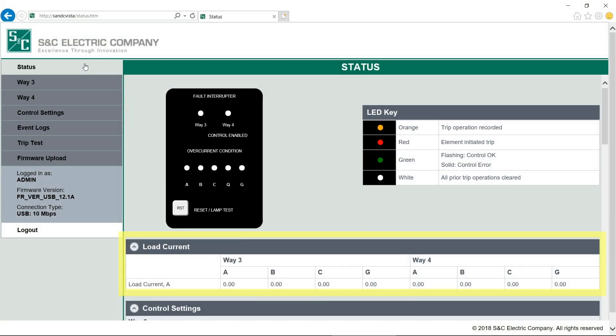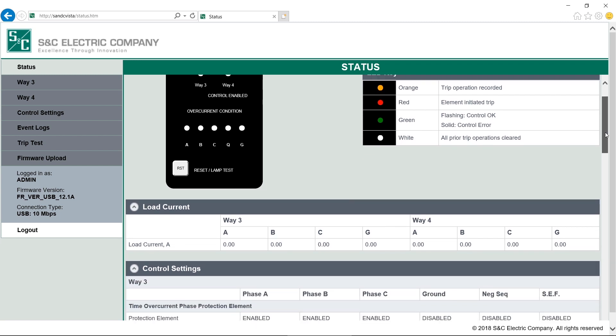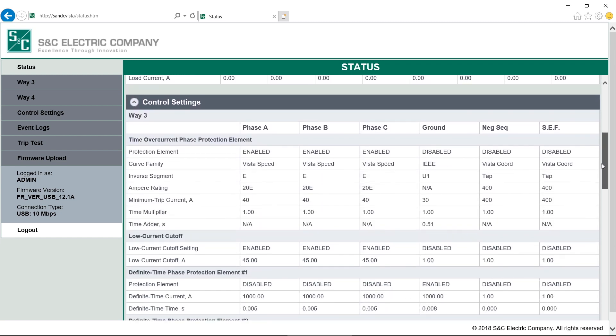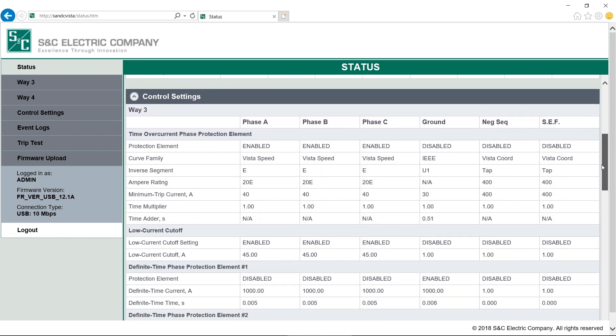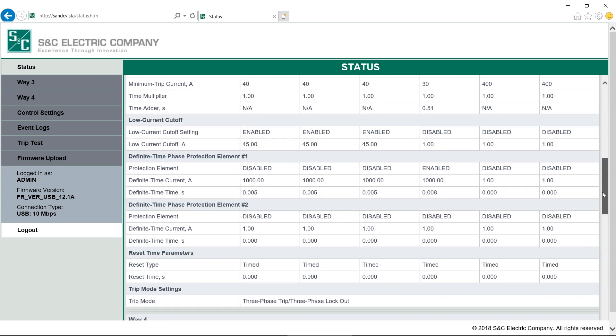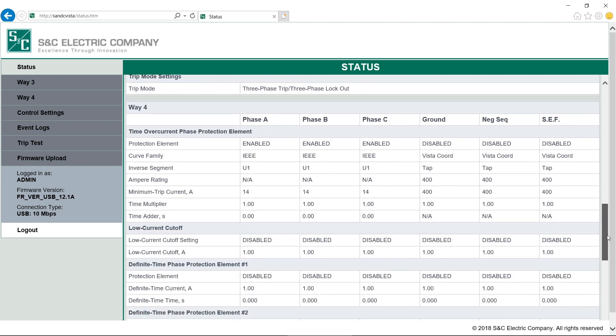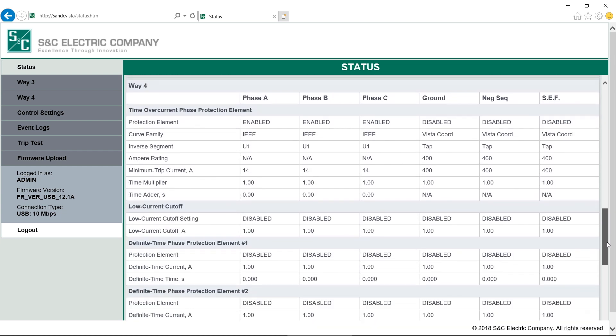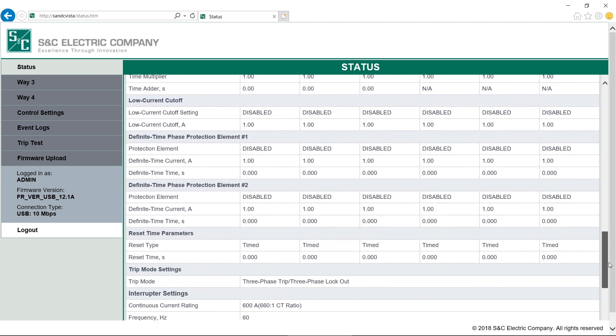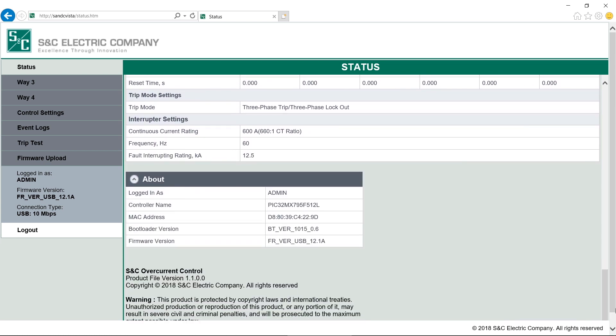The load current menu shows a snapshot of the load current going through the two interrupting ways or through ground. It can be refreshed by clicking the reset button. Below the load current, we can view control settings. These settings cannot be edited from here. If we were logged in as viewer, this is where we would go to check the settings. We'll show you how to program these settings later in the video. And at the bottom, we find the About section, which lists the login we're using, the controller name, Mac address, the bootloader, and firmware version. That's the status screen.